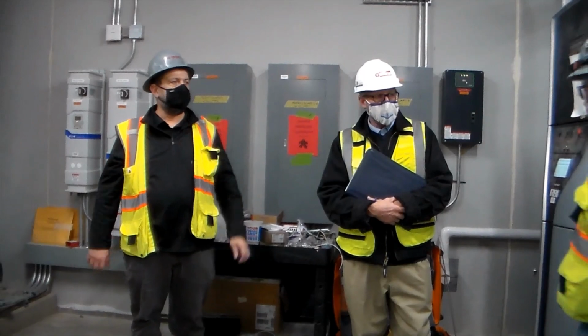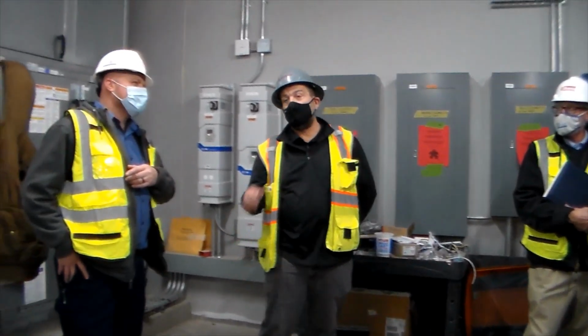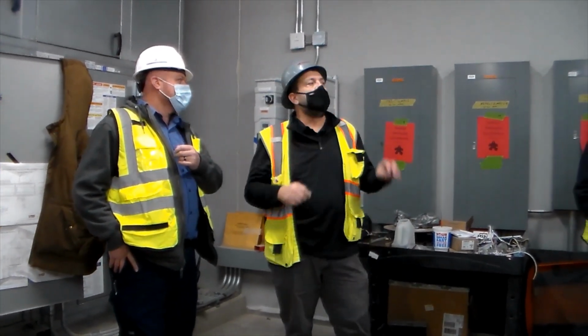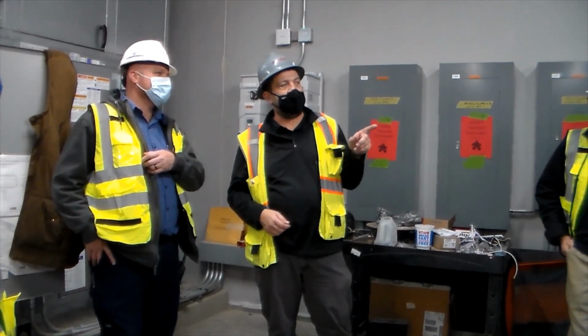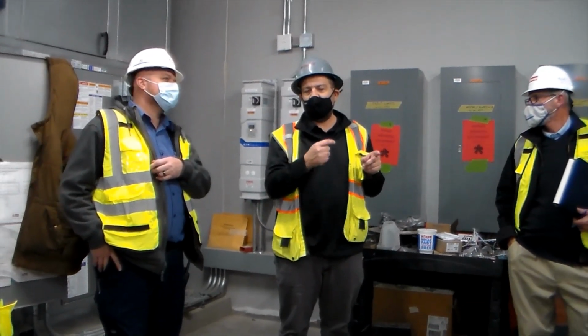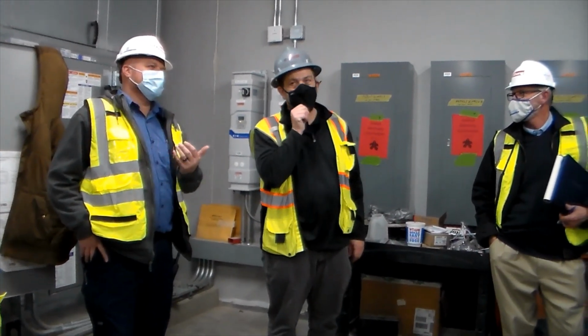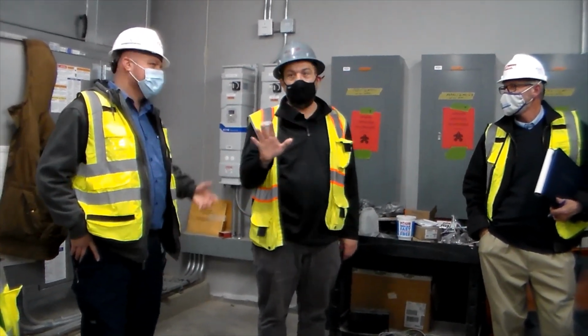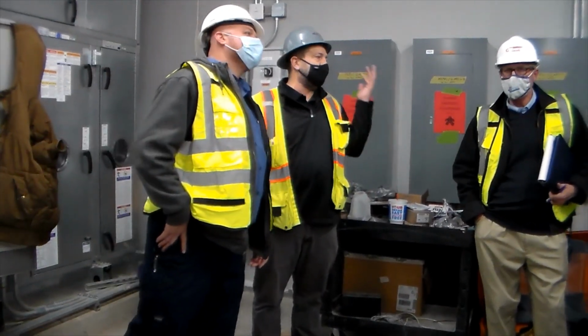Each of these has a display. The pump on the boiler changes. You will see the secondary pumps, but you will not see the primary pumps unless I can pick them up over BACnet. My understanding was that they said the signal would be so small that we would never see it when we tried to put a CT on. Basically, if the pump goes out, we'll get an alarm on the boiler. I believe that you will, I need to verify that. You have a water flow problem. Yep. If you have water flow, it'll show up somewhere.